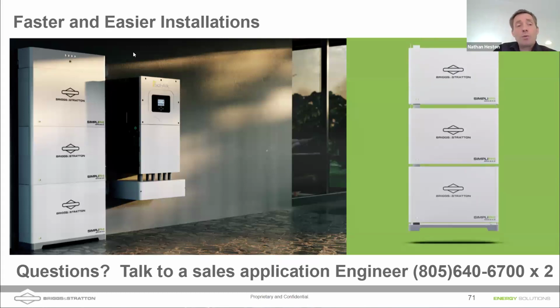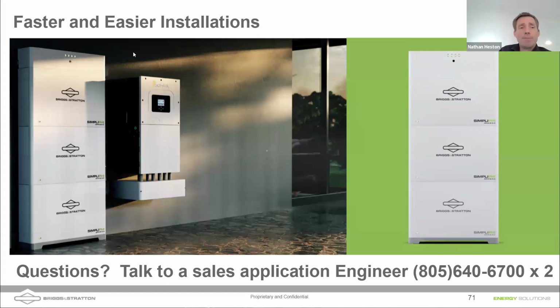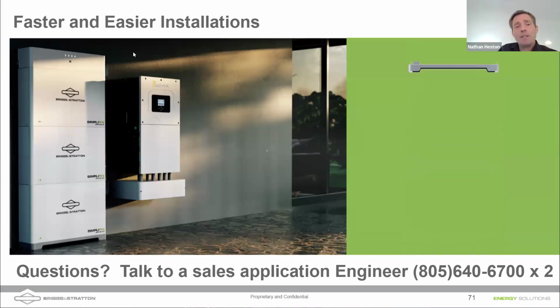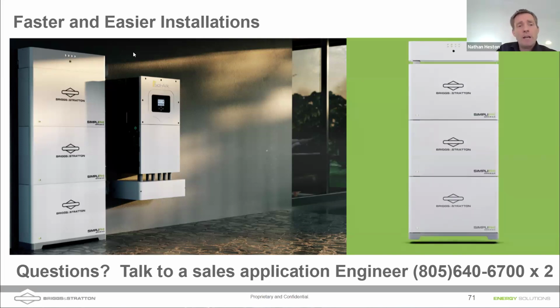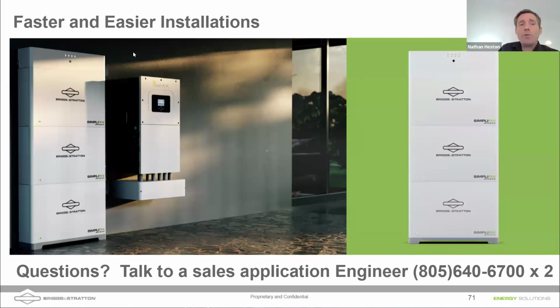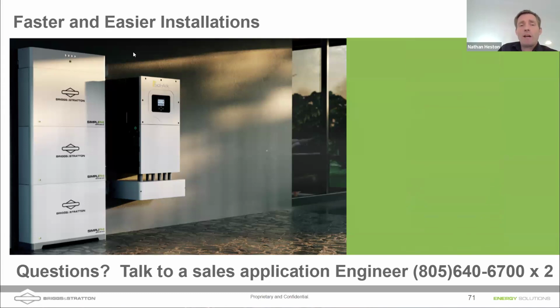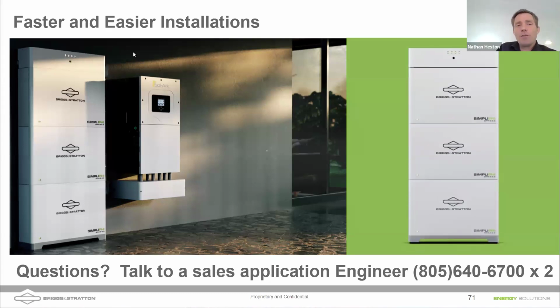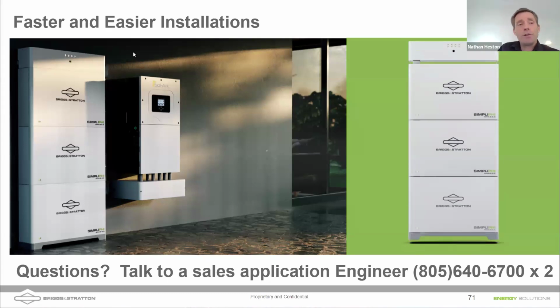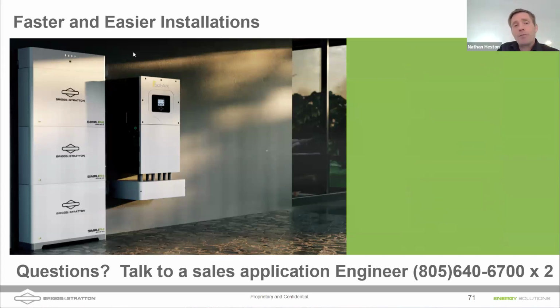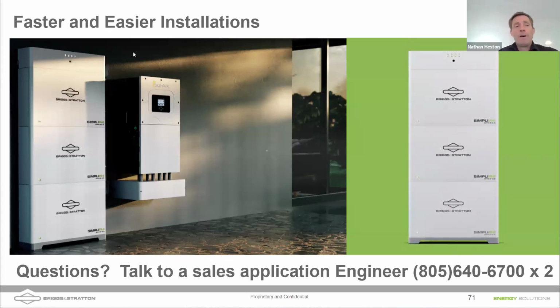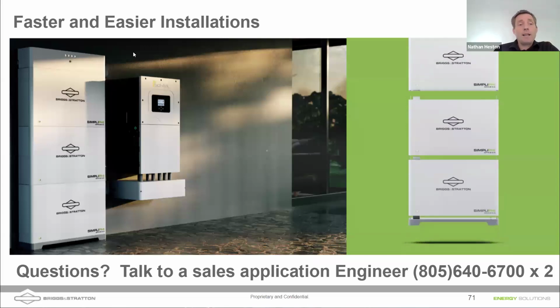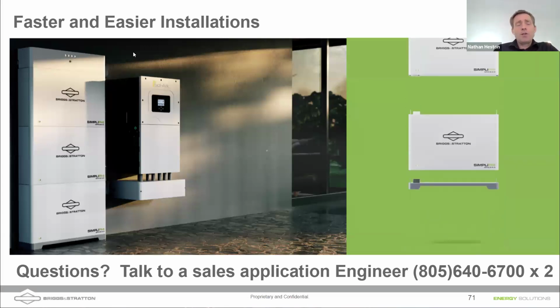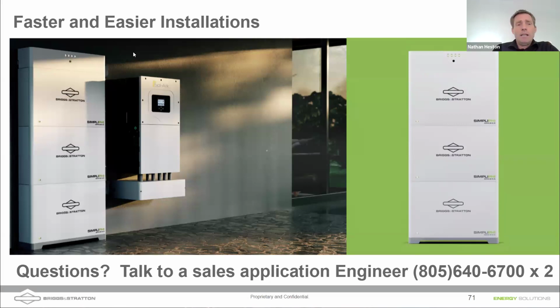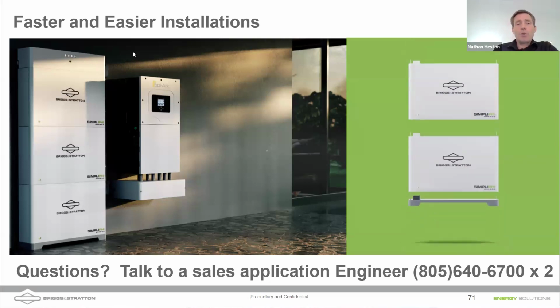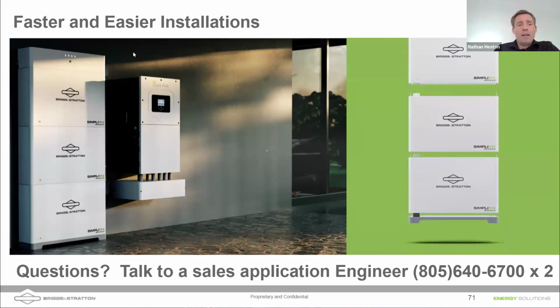Yeah, you can do that, which will tell you something about the internal resistance, Bill. We can even do a capacity test on each individual battery by running a load through it. You want to do this with specialized equipment. You can't really do that by running it through the inverter because of some inefficiencies of the inverter, but running it through the inverter will give you a rough idea. So yes, it is a good idea, especially if you're testing your own banks or somebody else's banks, to occasionally run these tests and check on health.